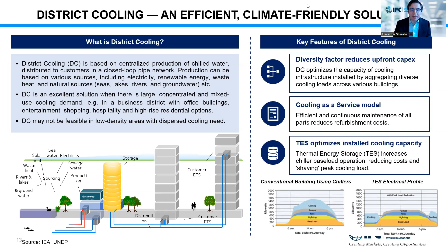The other big part of district cooling systems is that they enable thermal energy storage, either chilled water or ice storage. Basically, to visualize it, it's a big building - depending on size it can be up to 5 stories tall. What it does is shave off peak cooling demand, which translates into the need for less installed capacity and less peak power demand on the national grid, which in emerging markets can be a big challenge.